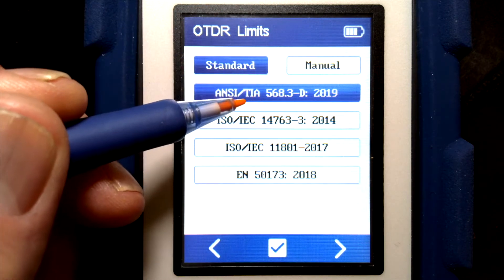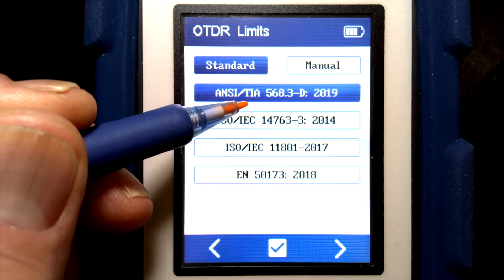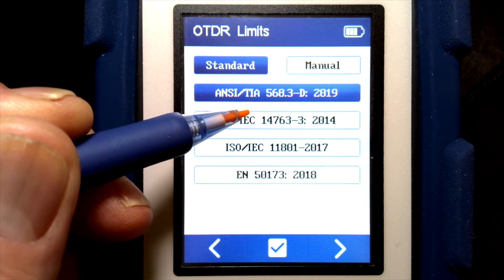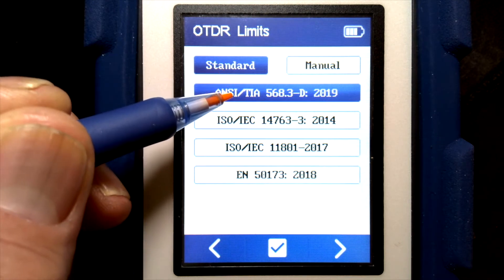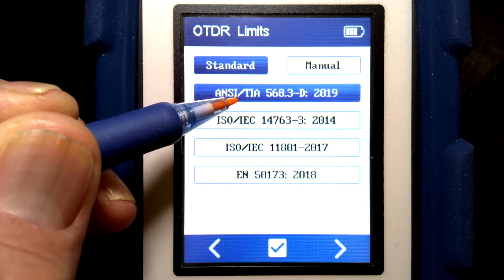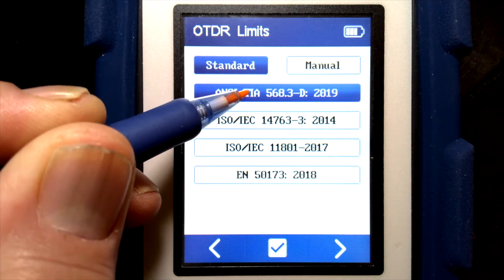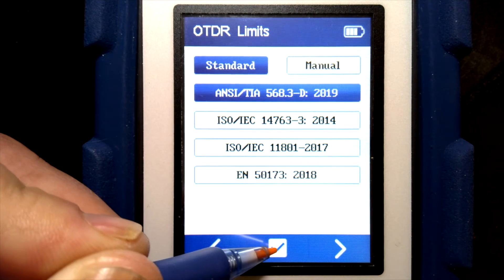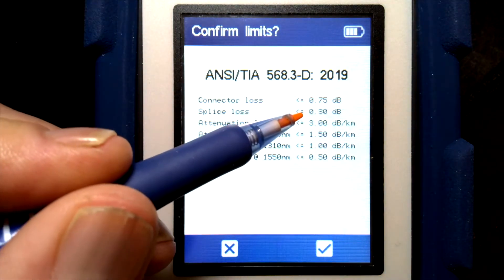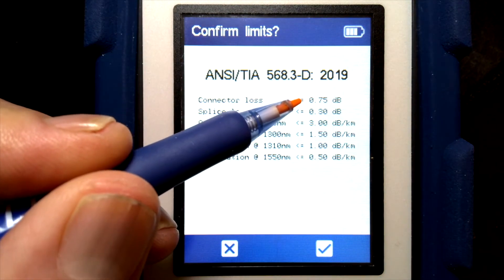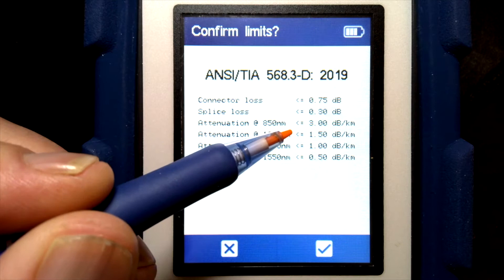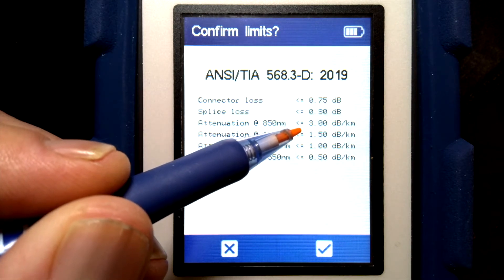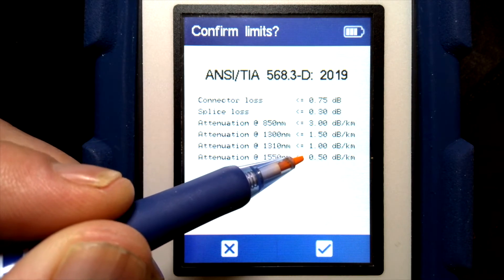These standards are based on the cable length and the amount of connectors and splices in the fiber. For each of these, if I choose TIA and hit OK, it's going to come up and give me options for connector and splice loss, as well as the attenuation for the fiber itself.